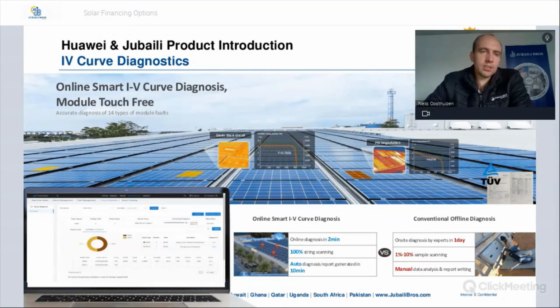Moving on to the next one. The next slide focuses specifically on IV curve diagnostics. The Huawei Smart IV Curve Diagnostics is an AI-powered solution, meaning that it scans your whole system and compares it to the normal state of how the graph should be, or it will compare your graph to what we know as being a PID or a diode that's been short-circuited. So all of this is done automatically, and it will then specify what the possible faults might be.